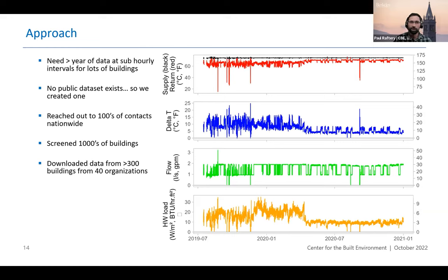Most of the buildings in the data set operate 90 to 95% of the hours of the year with a pretty much static set point — a clear indication of a problem that could be captured by fault detection systems. The good news is there's huge energy and carbon savings potential from very simple measures, even in the absence of an in-depth fault detection system or even with a very limited automation system. Measures like basic system scheduling, correcting zone airflow minimum airflows, correcting outside air controls, and implementing Guideline 36 resets in these buildings can have a very large cumulative effect — without having to do major equipment replacement like replacing a boiler or switching out a boiler for a heat pump.